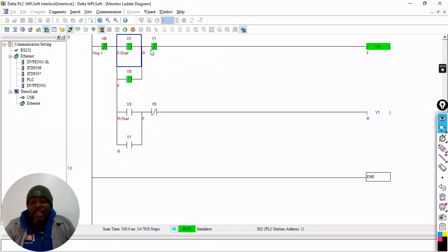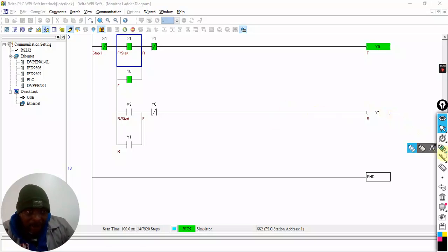So I think this is so straightforward. This is your forward reverse. But as you can see, it will only be easy to understand the forward reverse once you've looked at interlocking and you understand the interlocking. Because there again, is our interlock. If you check, there is our forward reverse interlocking there. These two are doing the job of interlocking. The symbol for the interlock is a little triangle like that. Unfortunately, we also use it for Delta, so a little triangle like that to show that those two are interlocked.